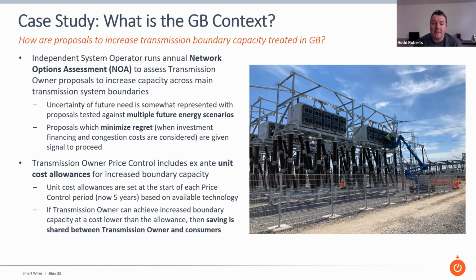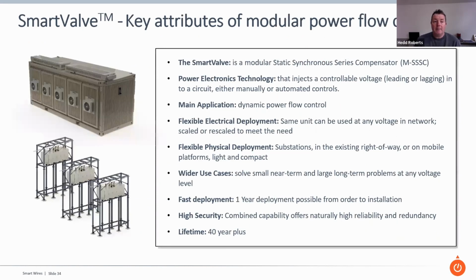So the main modular power flow control device that SmartWires is responsible for is a static synchronous series compensator. It's modular - essentially a power electronics device which injects a controllable voltage, either leading or lagging, giving control over the effective impedance of the circuits the smart valves are connected into.